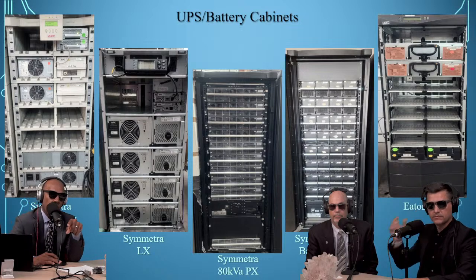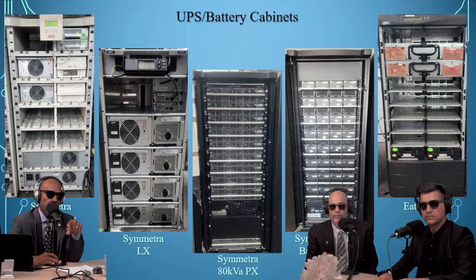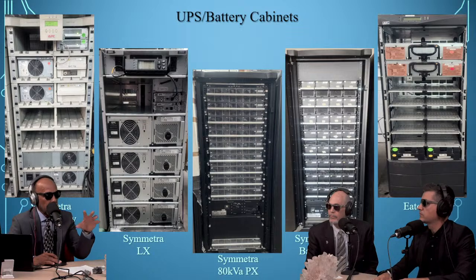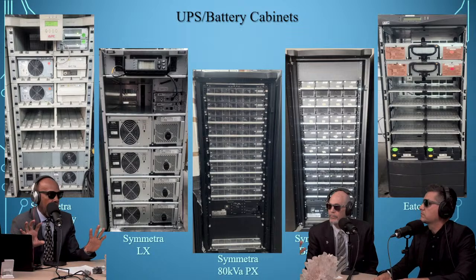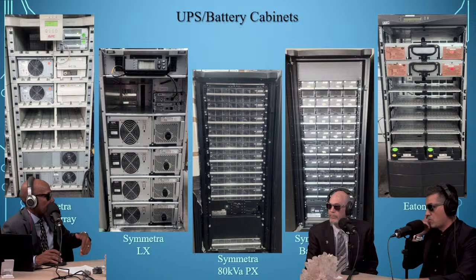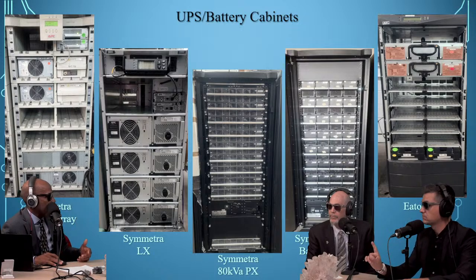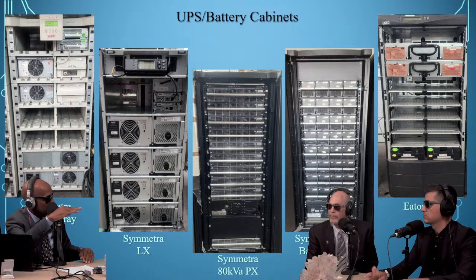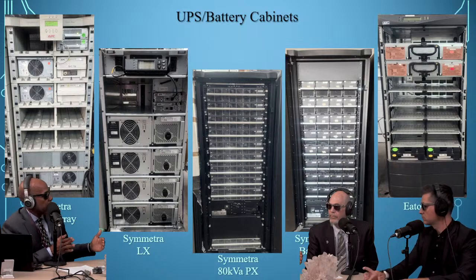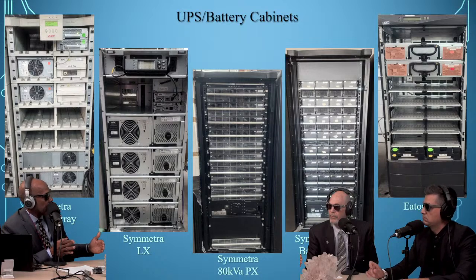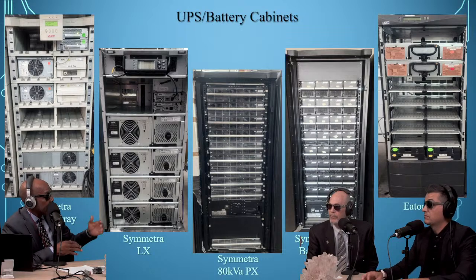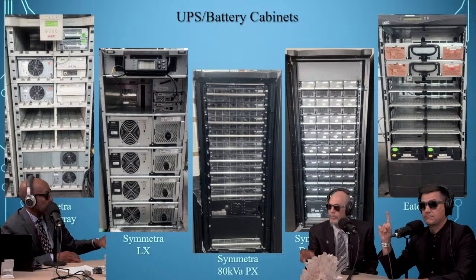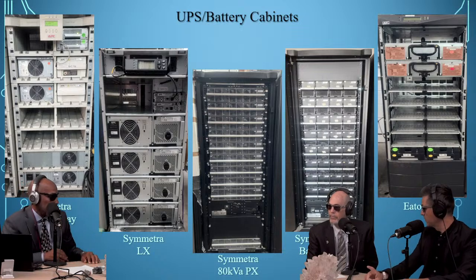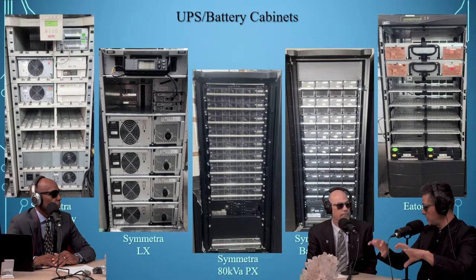Now we don't have a picture of a component UPS, but if we did you'd see the UPS itself and another battery cabinet, with a wiring apparatus, cables, five rows — you're talking 100-pound batteries, 50-pound batteries, 60-pound batteries all wired together in series. That entire series is the key word — all 40 of those cells are considered one string, because of the way they're connected together.